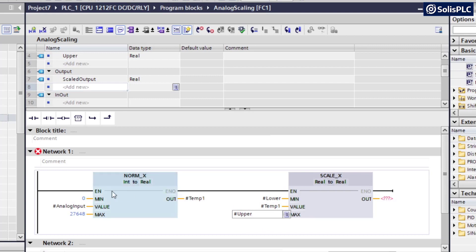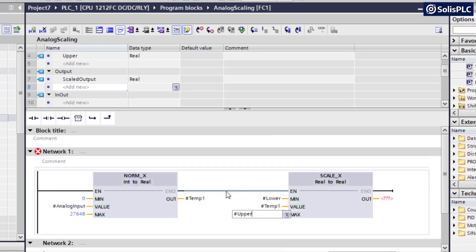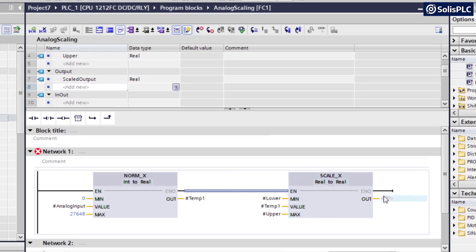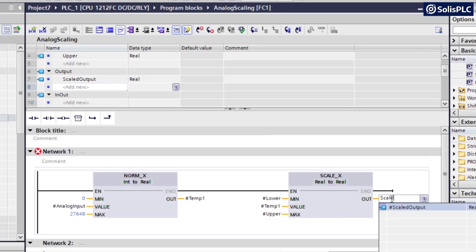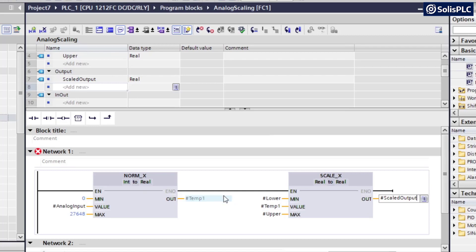So it's possible that you will have the analog input that's going to be, for example, analog input number 2. And instead of scaling from 0 to 10 meters, like we're going to do in this example, you want to scale from 0 to 50 kilopascals based on a pressure sensor. So that's going to be different as well. And this is going to drive a scaled output.